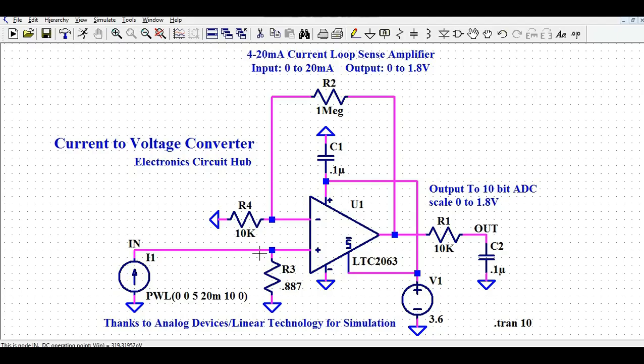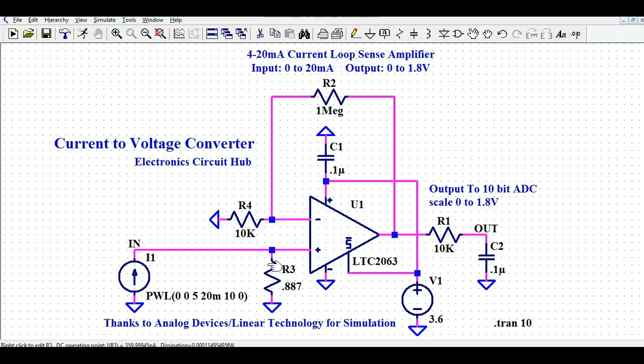Based on your current input — 0 to 20 mA or 4 to 20 mA — there will be a voltage drop across R3, the shunt resistance. The value of the shunt resistance is 0.887 ohms. Based on this voltage drop, we apply the virtual ground concept, and the same voltage drop across R3 will appear at the voltage across R4.